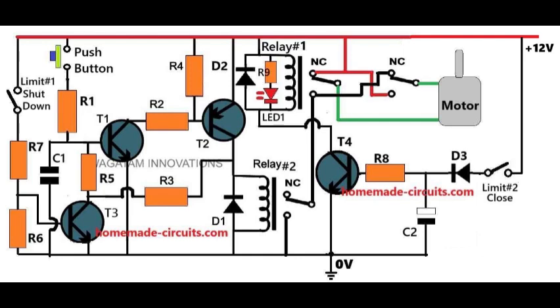With limit number 1 no longer pressed, T1 and T2 can finally latch, ensuring relay number 2 stays on even after the push button is released. The motor continues running until the door reaches its fully open position. At this point, the door mechanism presses limit number 2, triggering the next stage.